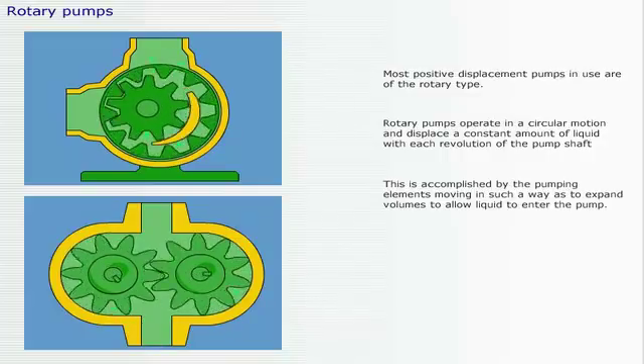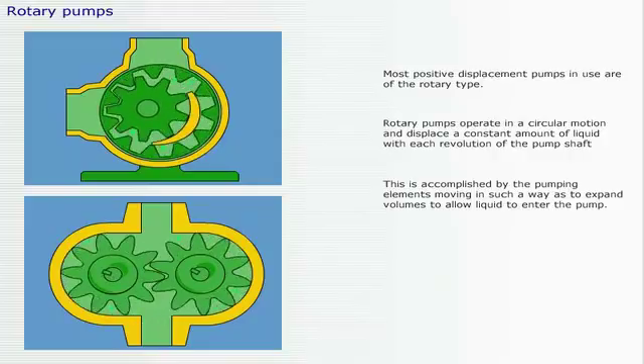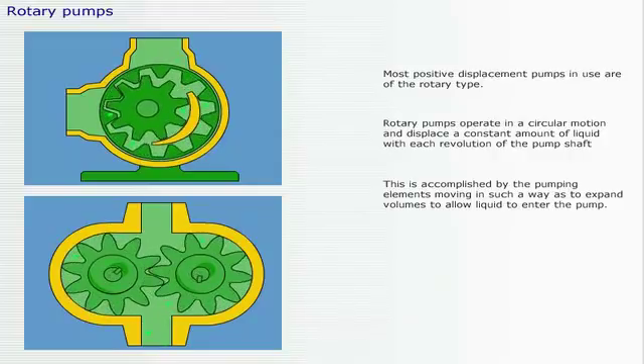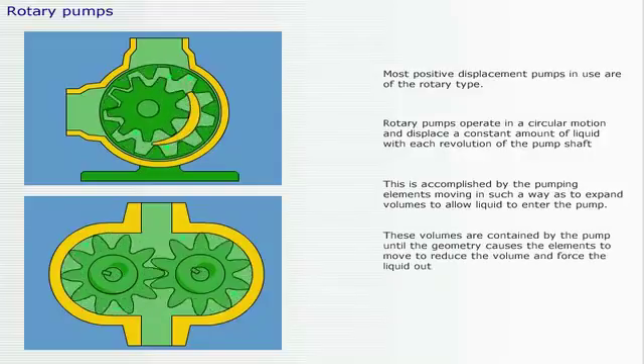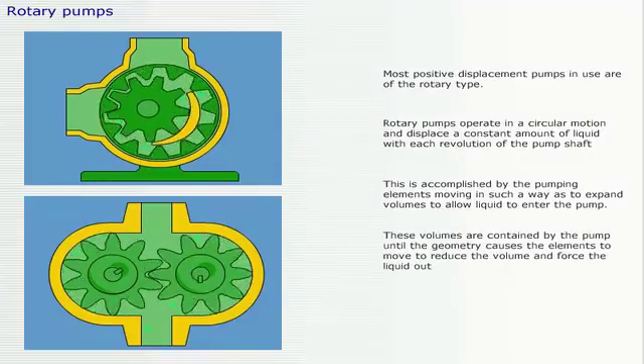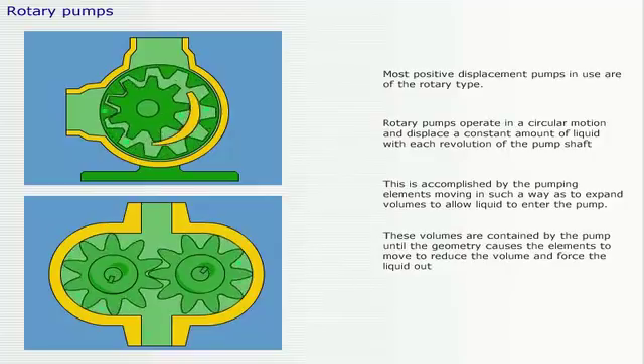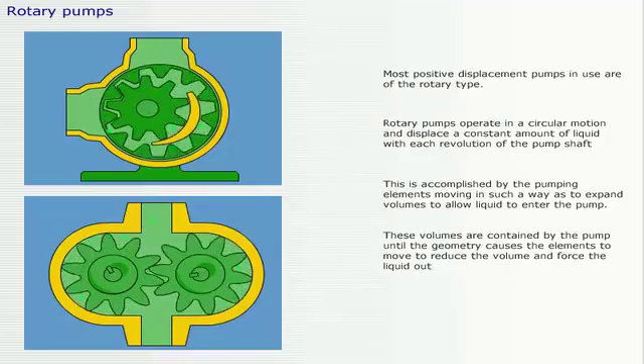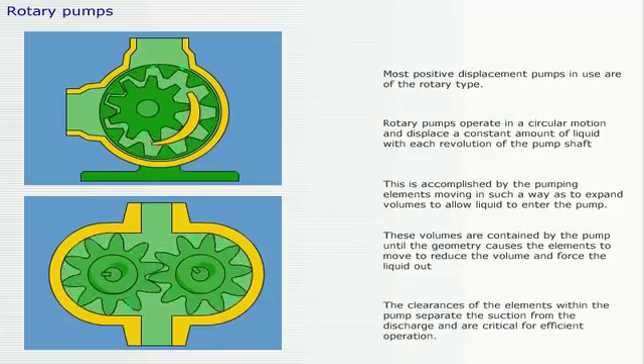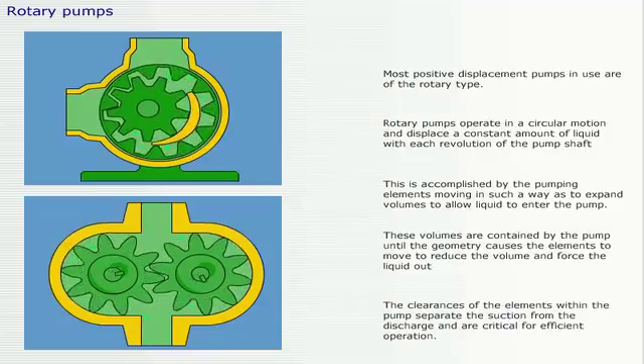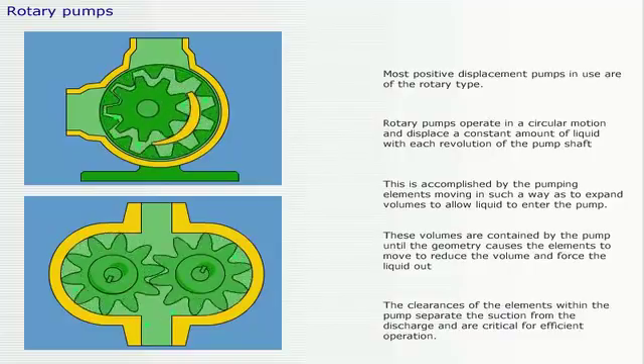This is accomplished by the pumping elements moving in such a way as to expand volumes to allow liquid to enter the pump. These volumes are contained by the pump until the geometry causes the elements to move to reduce the volume and force the liquid out. The clearances of the elements within the pump separate the suction from the discharge and are critical for efficient operation.